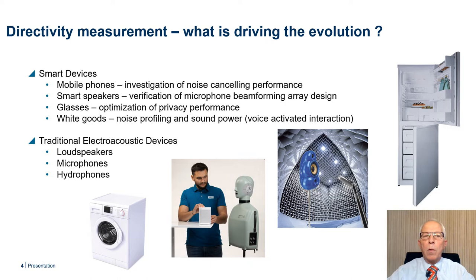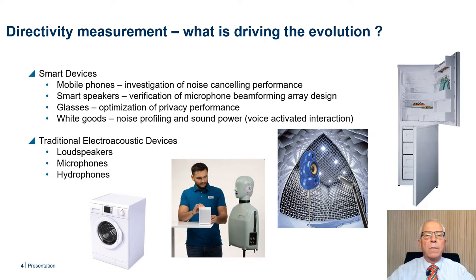The need for directivity measurements has become increasingly important as more and more devices become smarter and intelligent. For example, consider mobile phones, where investigations of noise-canceling performance in both sent and received directions call for testing in artificial noise environments, typically simulated by a loudspeaker setup. Under certain circumstances, it could be relevant to examine the noise-canceling performance from various directions. For smart speakers, verification of microphone beamforming array designs is another area that requires directivity measurements. For optimization of privacy performance, for example in glasses or headphones, directivity measurements are relevant as well.